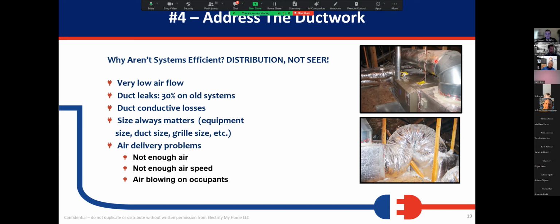The other thing on heat pumps is we want to use the right type of grills and get the airflow right. Use high flow return air registers and increase the return air sizes. For anything up to 3 tons, we should have 600 square inches of return air opening to keep the velocity low, so that we're not making noise, number 1, and causing drafts, number 2. And then we solve all those problems: not enough airspeed, not enough air. Make sure we use the right registers so that we're not blowing the air on the occupants.